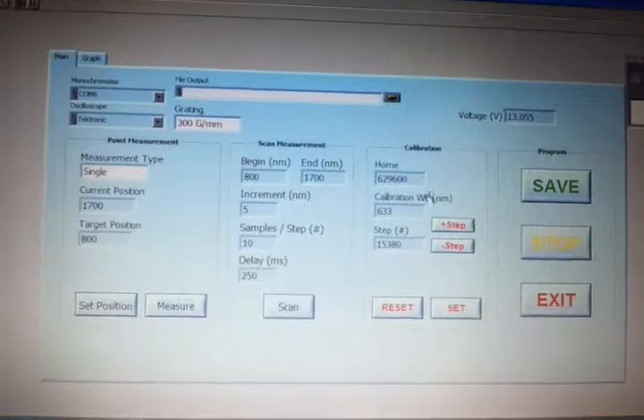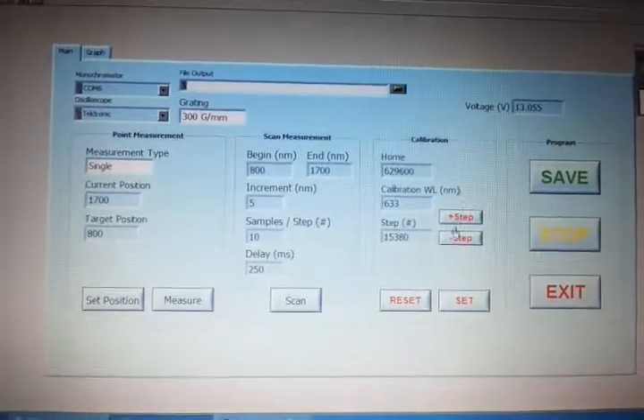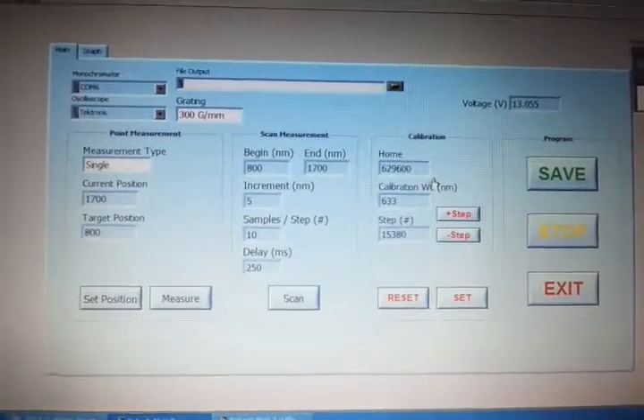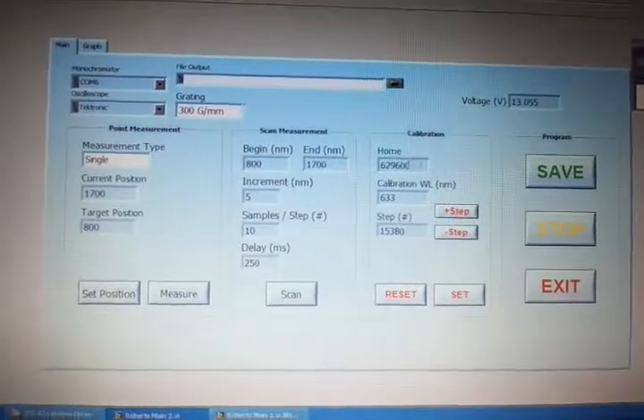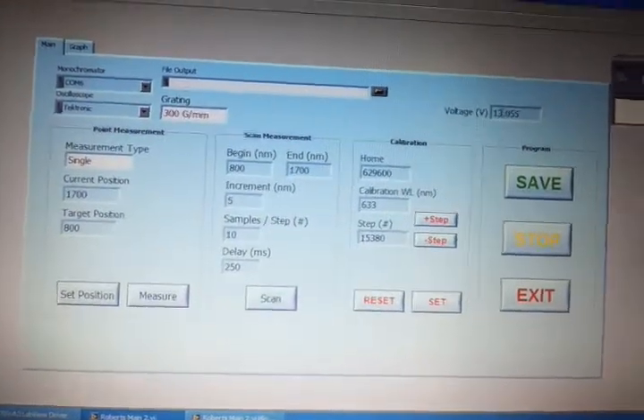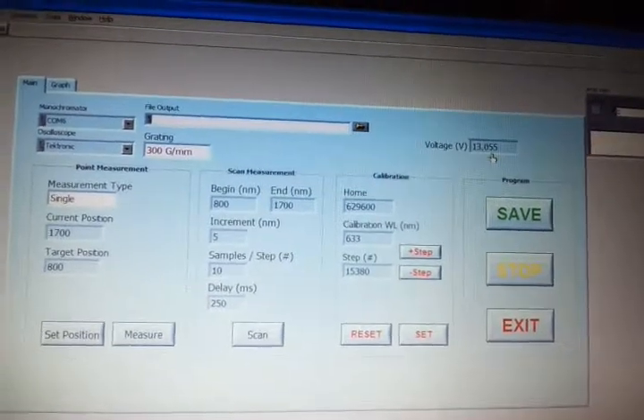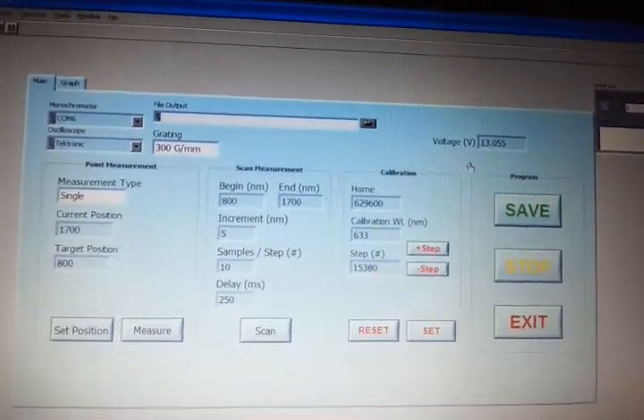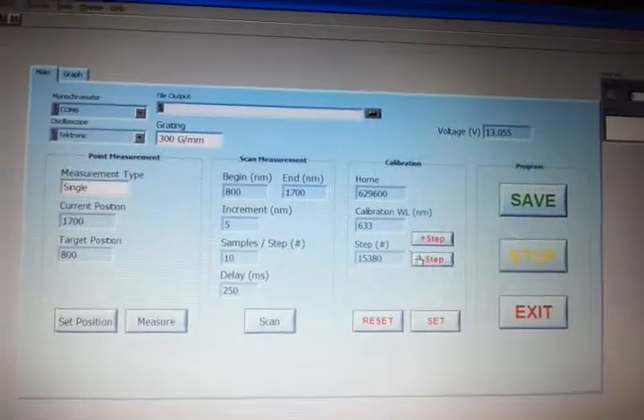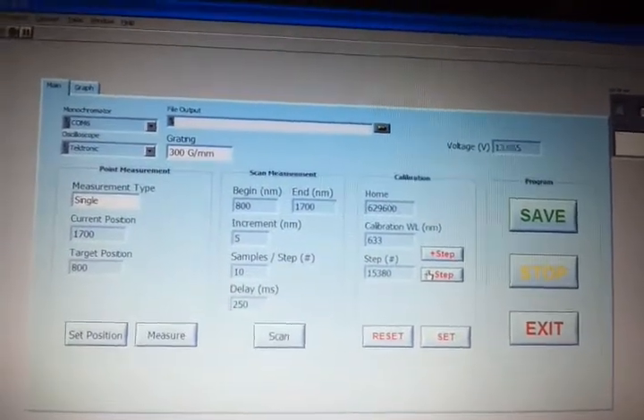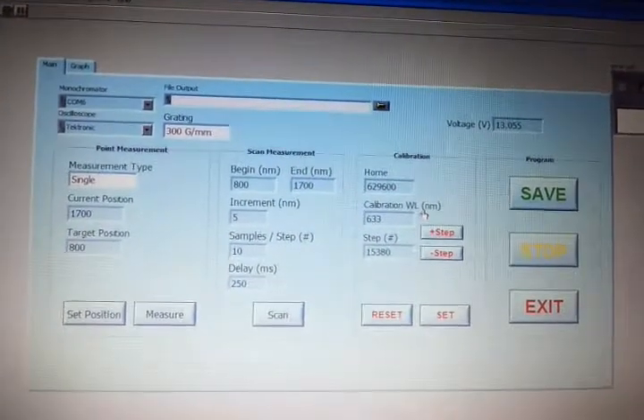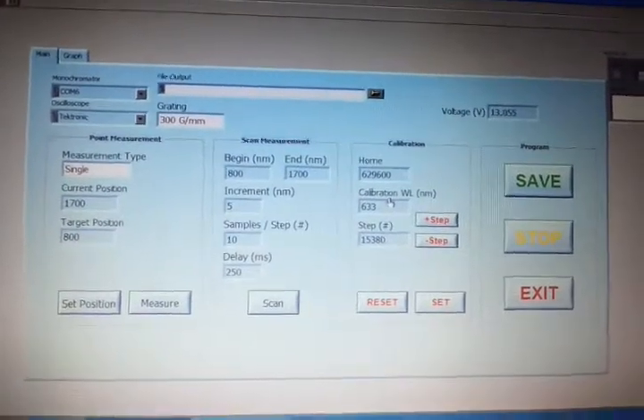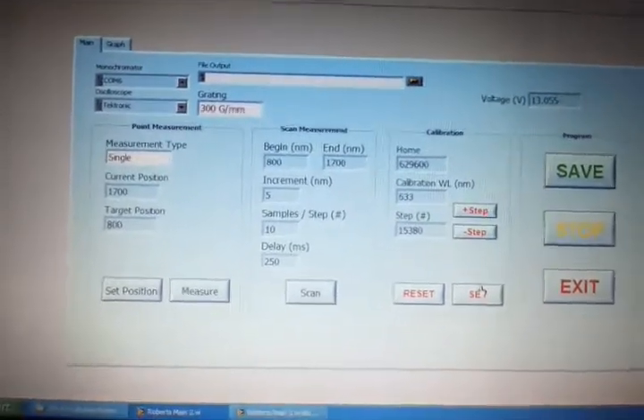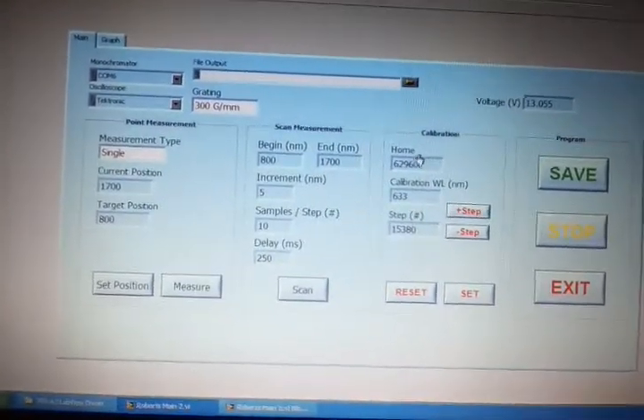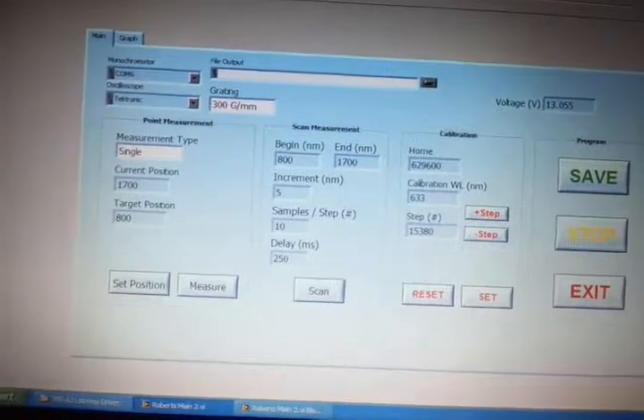You can go to this home position and then add or subtract any number of counts from this until your voltage output is at a maximum that corresponds with your driving wavelength. Once you are satisfied that you have reached a maximum and that the counter number here corresponds with your wavelength, click set. That then sets the new counter number as the home position.